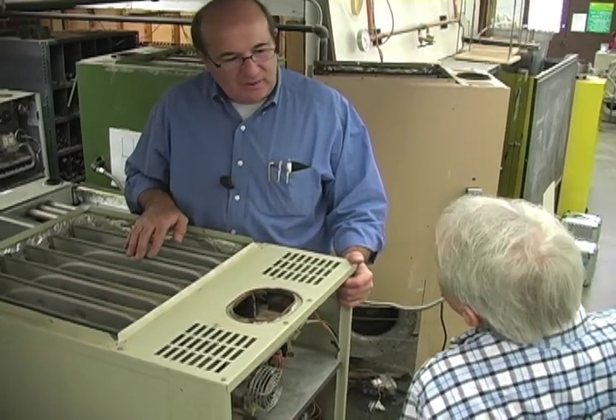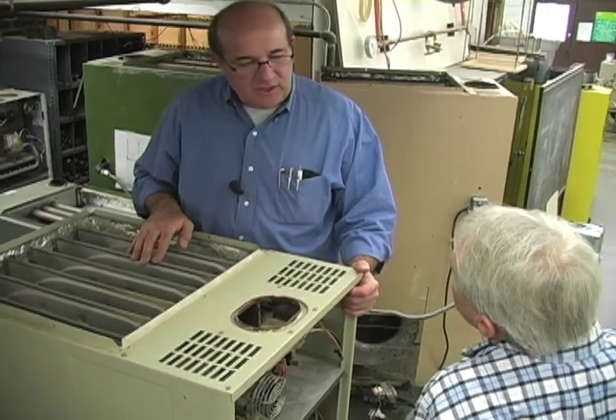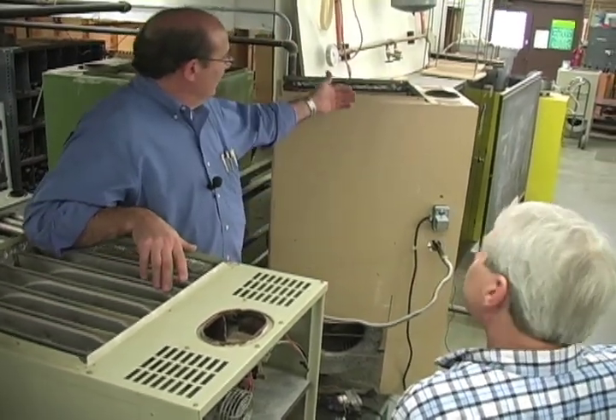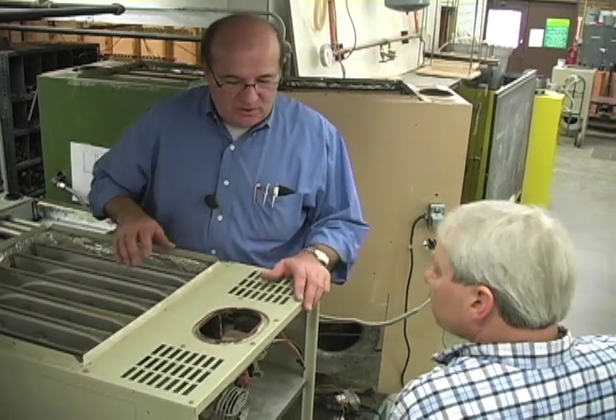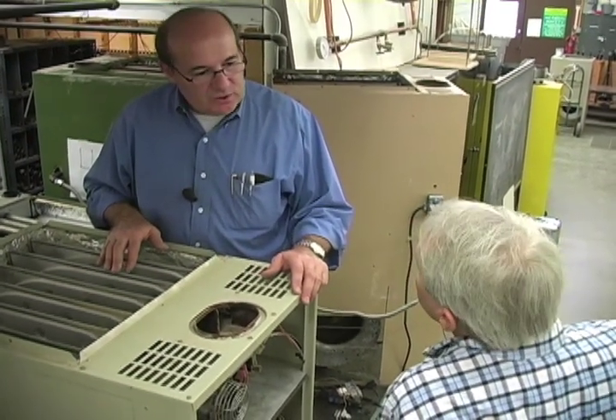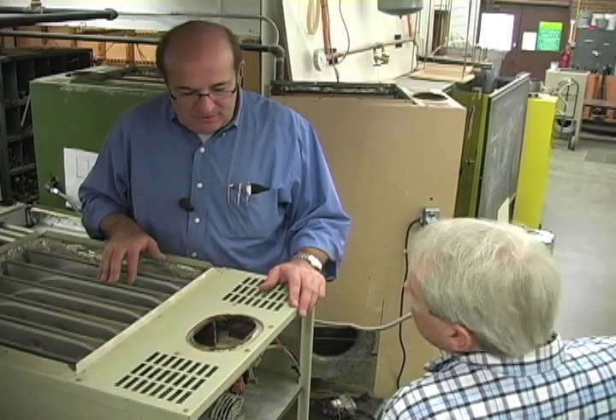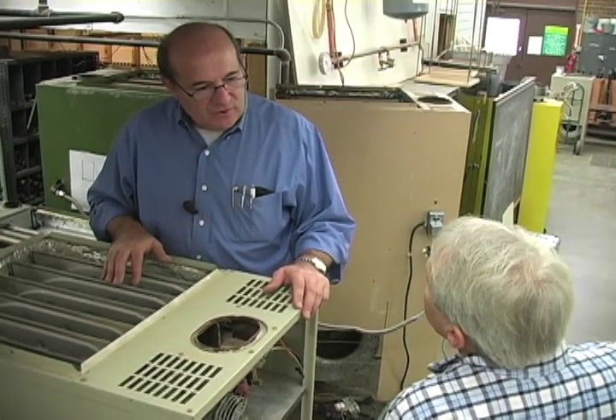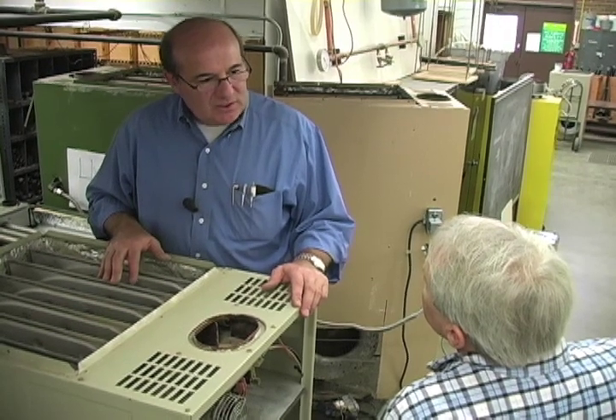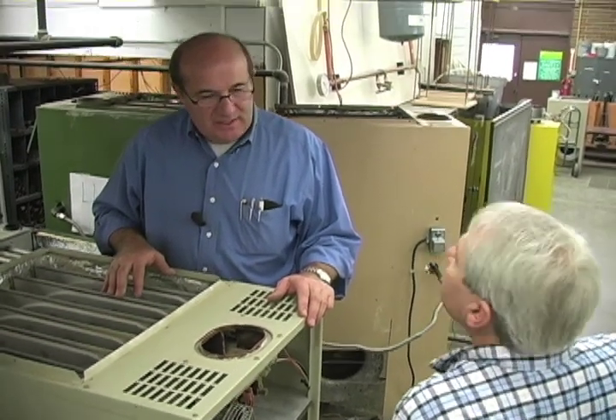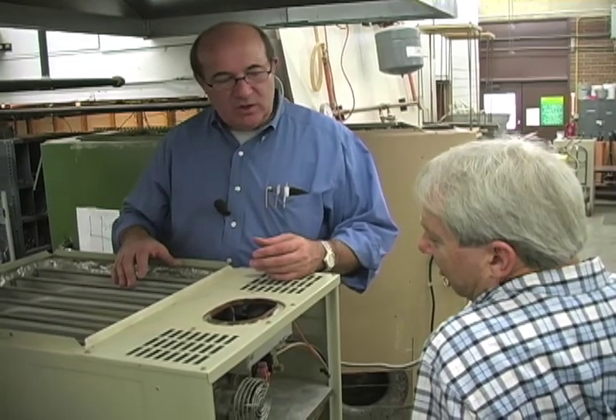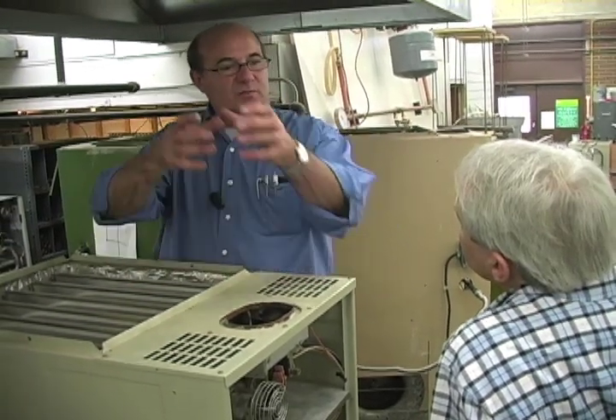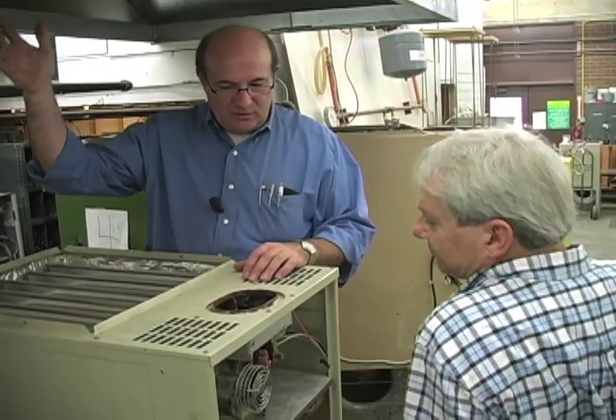One of the things that we see an awful lot of is the older style furnaces. Certainly these old gravity type furnaces have much bigger flues than the newer induced draft or forced draft furnaces. When you move a gas stream through a bigger pipe, it slows down the velocity of the exhaust gas. It tends to hold that gas in the pipe longer, and it gives it a longer period to condense back out. Right. Whereas if you've got a smaller vent pipe, that gas flows more rapidly out, and before it has a chance to cool down, it's exhausted through the house or through the roof.